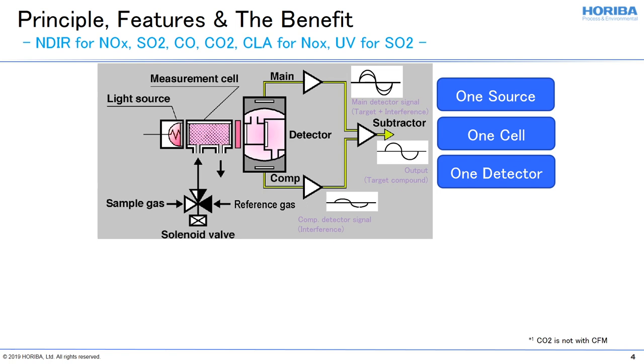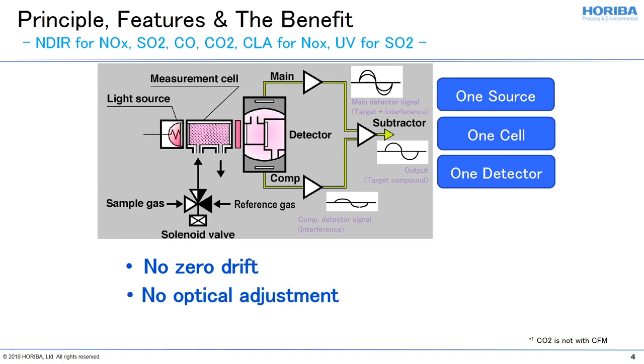Even if a dirty cell exists causing drift, the detector reads it as zero — hence drift is cancelled. This is why Horiba's cross-flow equipped analyzer has zero drift, and therefore no optical adjustment is required.